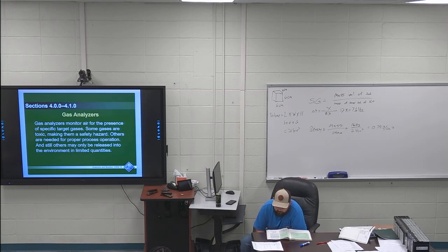Second paragraph, first 2 sentences. One type of high temperature electrochemical sensor commonly used in combustion control applications to determine the combustion, key in on combustion efficiency, is the zirconium oxide oxygen sensor. This sensor consists of a cell made of ceramic zirconium oxide combined with an oxide of either yttrium or calcium.